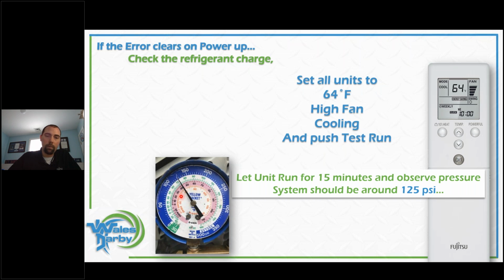If we look at the pink area here for 410A, our standing pressure is going to correlate to your temperature here. That's going to be your ambient temperature for the most part. So especially with mini splits, it doesn't work real good with traditional split systems, but with mini splits being in the living space, our temperature differences from outdoor to indoors isn't really that high. So we're going to be fairly accurate here, at least to get an idea. But if it's 60 degrees out, I should be at about 165 PSI, right? So on a 60-degree day, we follow the 60 degrees.